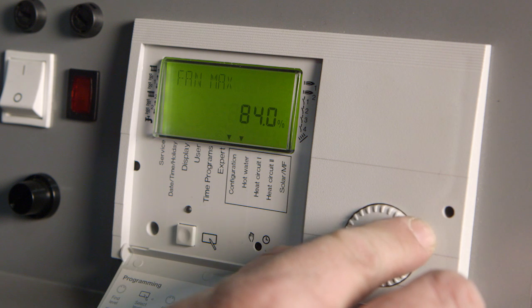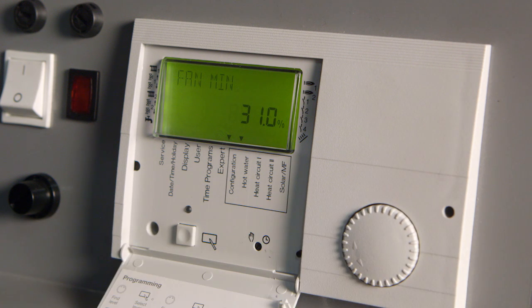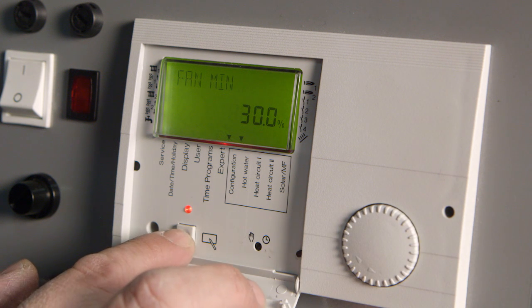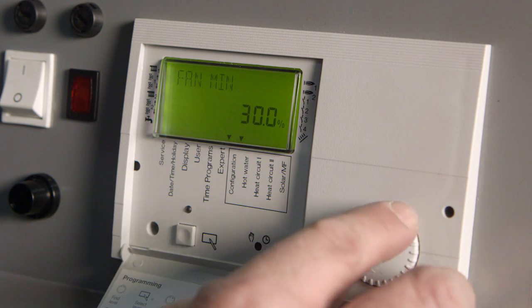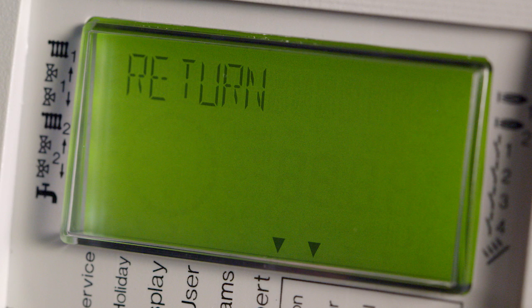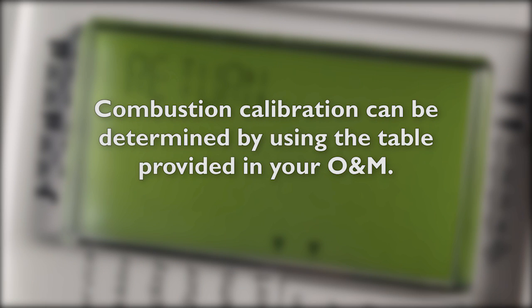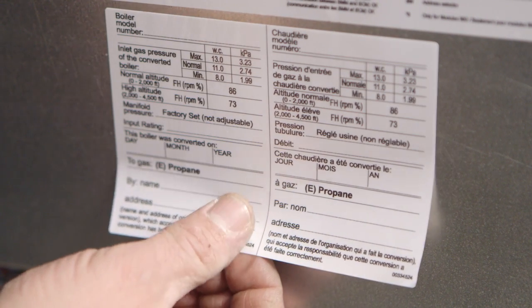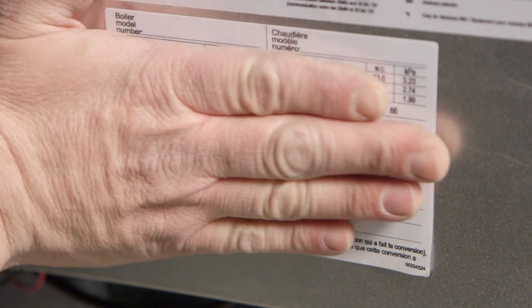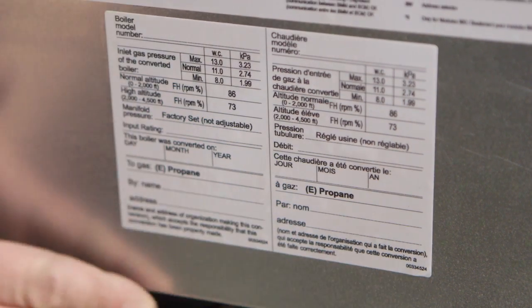Turn the wheel to scroll to minimum fan speed and set this value to 30 as shown here. Scroll the wheel to return to Exit Module 1 in the settings. Repeat this process for each module. Now you can proceed to the combustion calibration. Use the table provided in your manual as a reference for the proper conversion values. After the gas conversion of propane and calibration has been completed, the gas installer should complete and apply the label that looks like this one to the rating label.